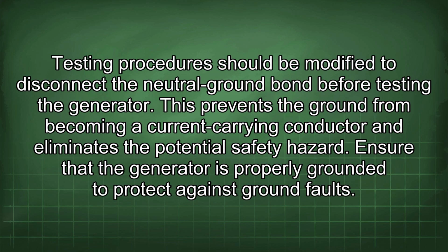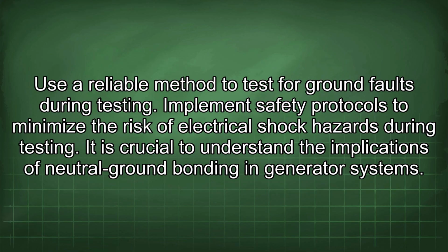Testing procedure should be modified to disconnect the neutral ground bond before testing the generator. This prevents the ground from becoming a current-carrying conductor and eliminates the potential safety hazard. Ensure that the generator is properly grounded to protect against ground faults. Use a reliable method to test for ground faults during testing. Implement safety protocols to minimize the risk of electrical shock hazards during testing.